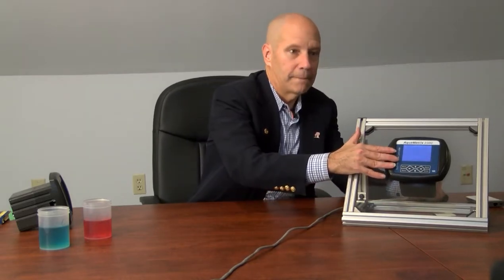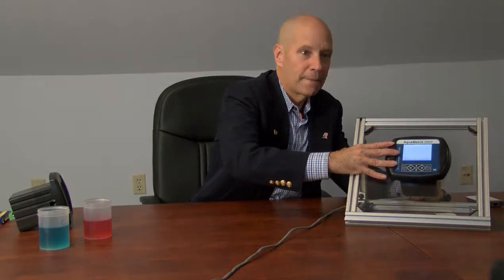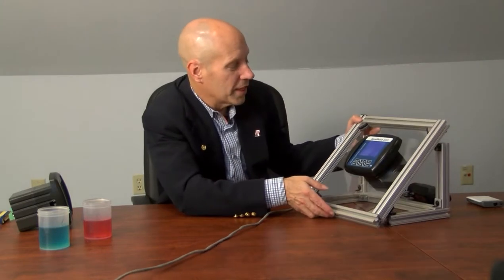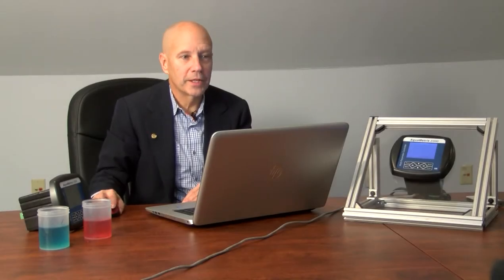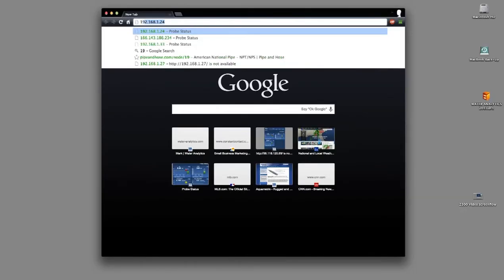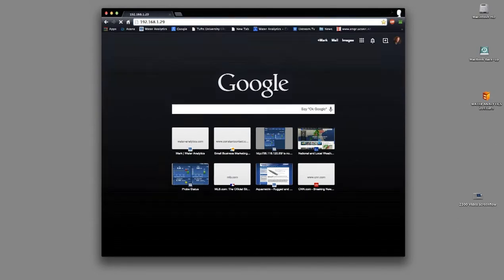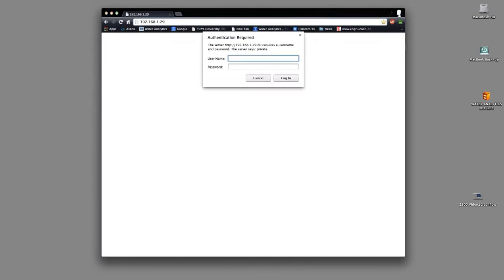Let's set up a 2300 using the web interface. I've already inserted an Ethernet cable into the unit, and now I'm going to plug it in. Notice that the first thing you see is that the front panel display announces that it has an IP address that my router assigned to it. And as you can see, that number is 192.168.1.33. So I go to my laptop and I'm going to type in that IP address, and the 2300 sends back a login window.